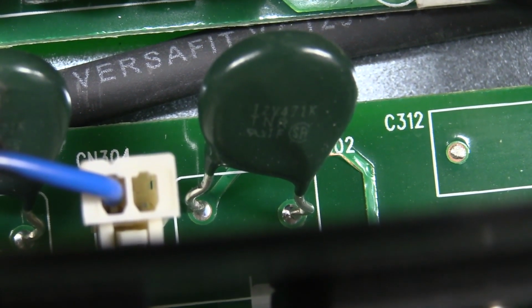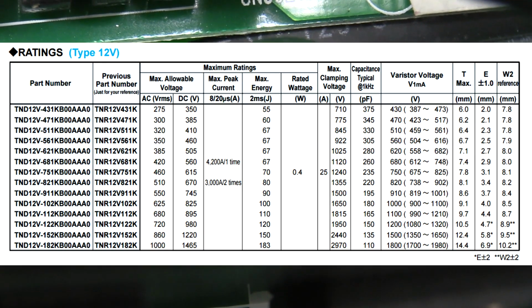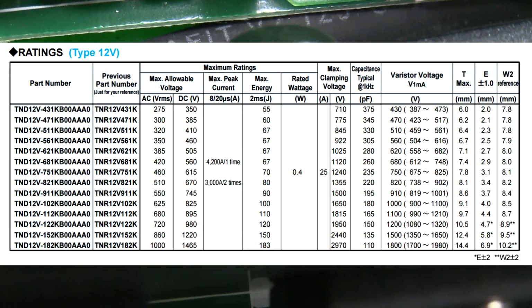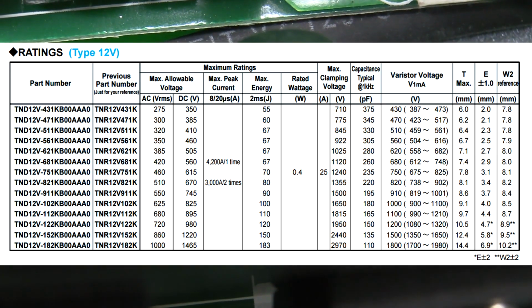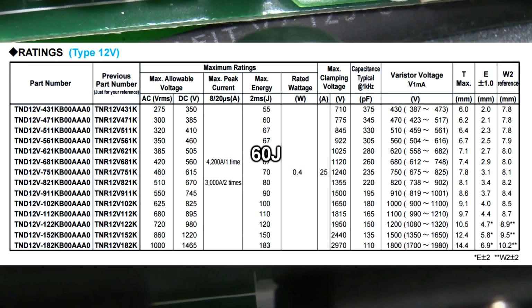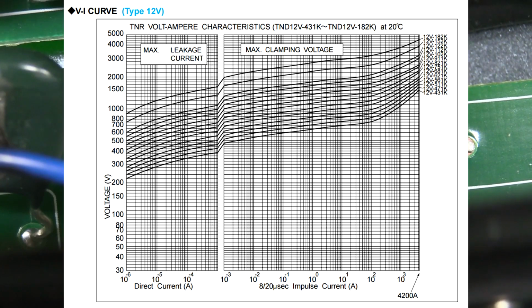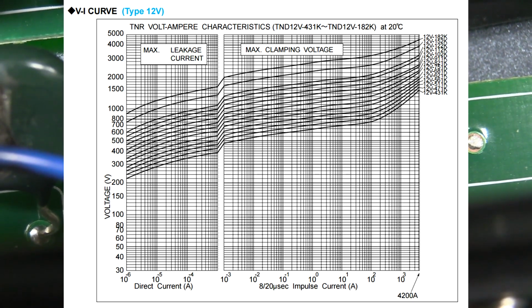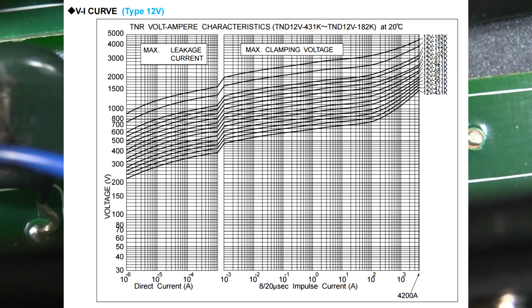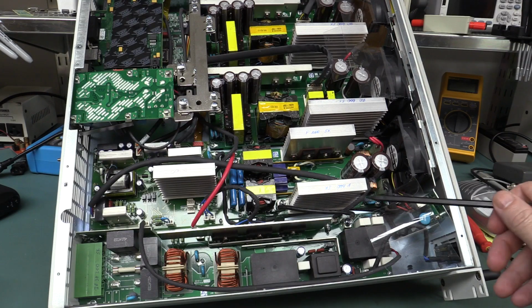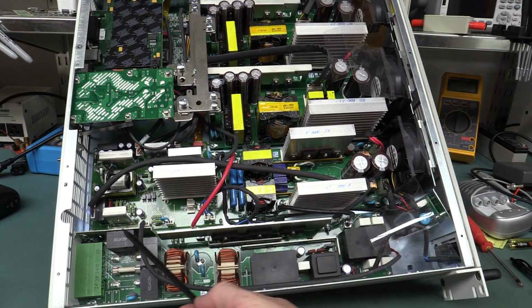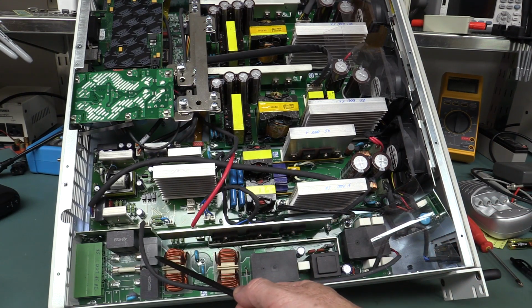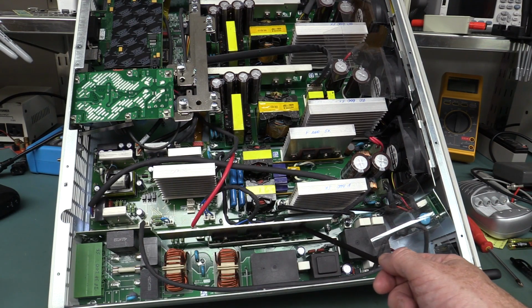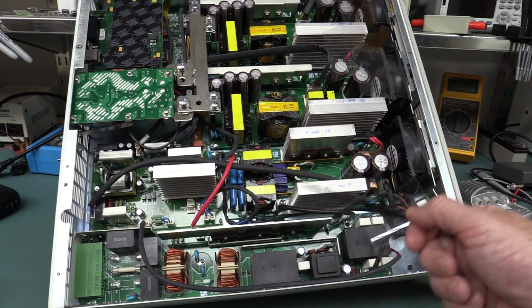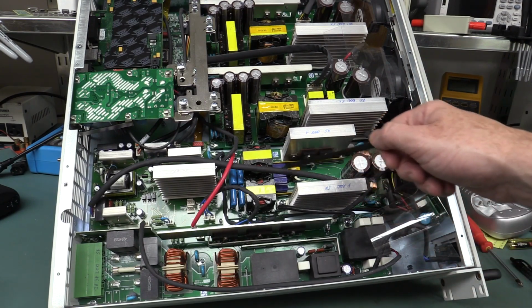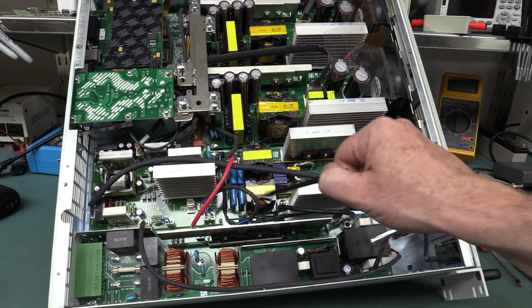And that puppy is actually a Nippon Chemicon MOV. That's a 470 volt nominal rating, hence the 471K there. That's a dead giveaway. And this one's a 30 joule job, so it's a bit beefy, but obviously, because you plugged in 400 volts AC in here when you rectify that. Oopsie! Now, just looking at the failure mode here, we know we put 400 volts per phase onto this puppy. So when you full wave bridge rectify that, of course, you convert it to DC, multiplying by 1.41 times, and it's going to jump over here via these big jumper cables I didn't show.